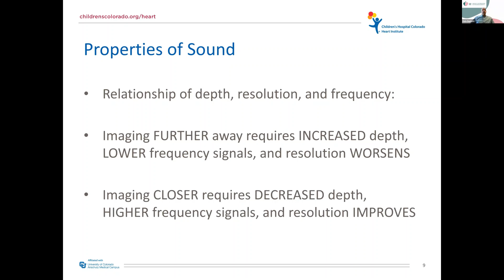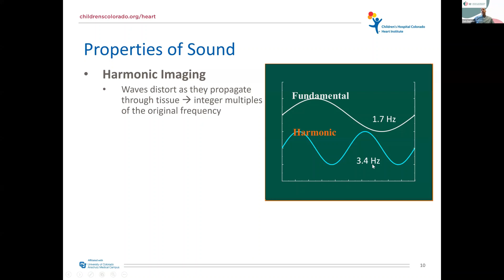Another interesting property of sound that's worth noting here is harmonic imaging. As these ultrasonic waves travel through tissue, they actually get distorted. They end up being distorted in integer multiples of the original frequency. So I'm just going to show you here, if the original frequency was 1.7 hertz, there will be frequencies in the tissue at 3.4 and other multiples of 1.7. We can actually use this to our strength because these harmonic frequencies can grow stronger with distance. And so when you're imaging things that are further away, focusing on harmonics can improve your signal to noise. The signal is the thing we care about, and the noise is all the things that we don't want to be imaging. So using harmonics can improve that signal to noise ratio.